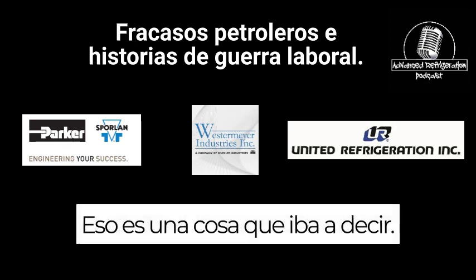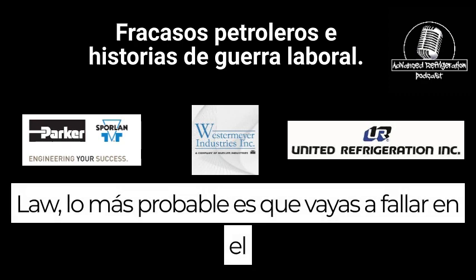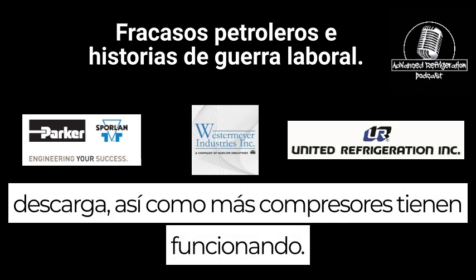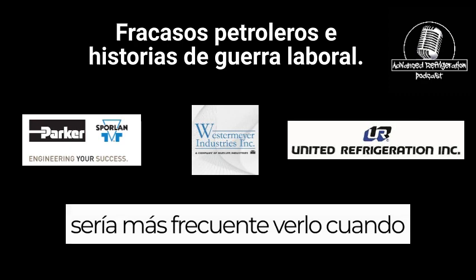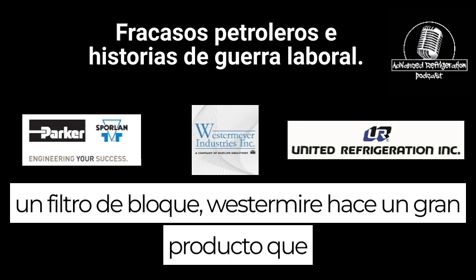Well, that's one thing I was going to say. To optimally check, because if you're going to have this fail, Murphy's Law, chances are you're going to fail in the summertime when your load is the highest. The higher your discharge, the higher your delta P is between production and your discharge, as well as the more compressors you have running. If you do have some sort of restriction, it'd be more prevalent to see it when all your compressors are actually running.